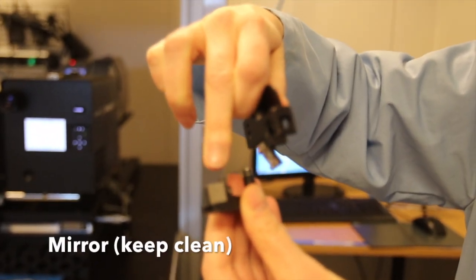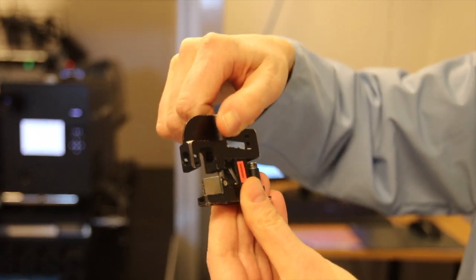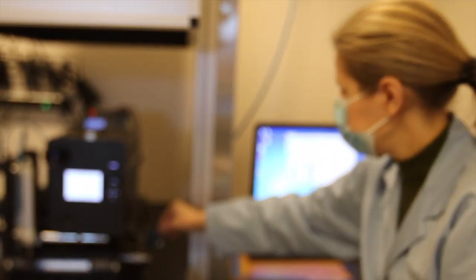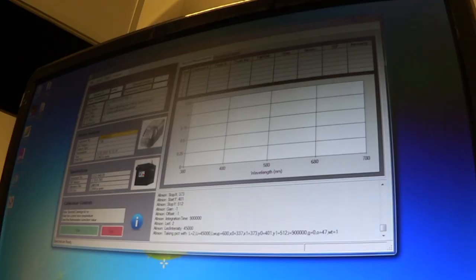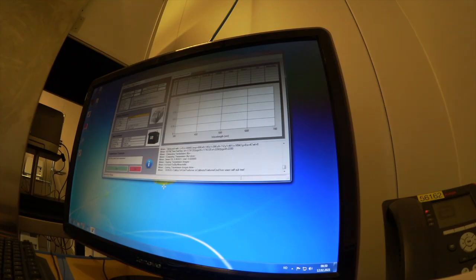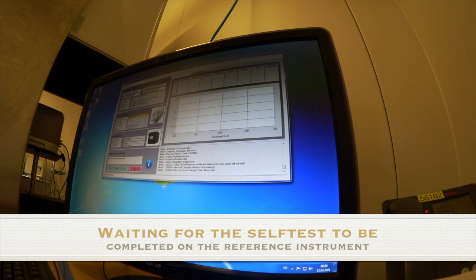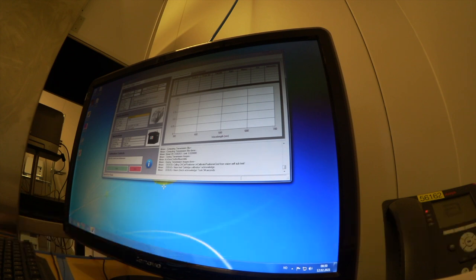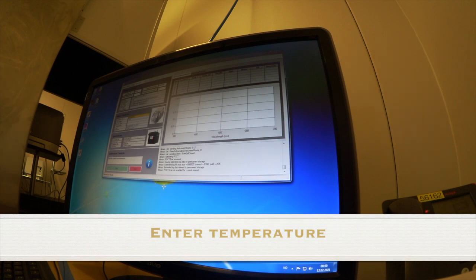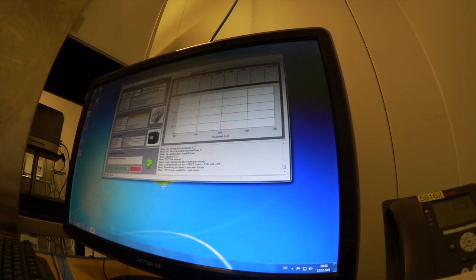Before you start calibration, you should inspect the mirror. If it is dirty, you must clean it, as described in the procedure. But you have to be careful so that you don't damage the mirror. Enter the room temperature in the GUI. You are now ready to start the calibration immediately after the self-test is completed on the reference instrument.